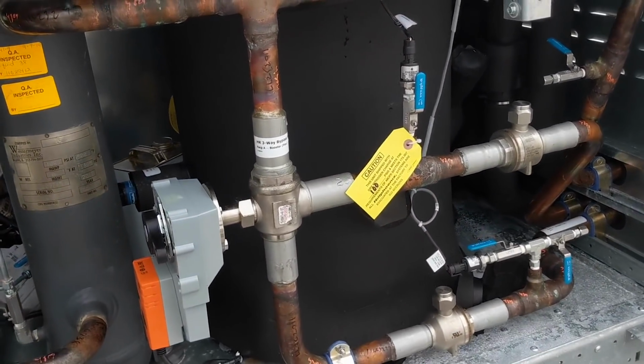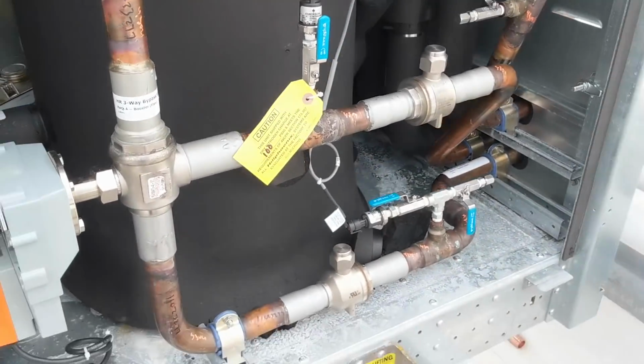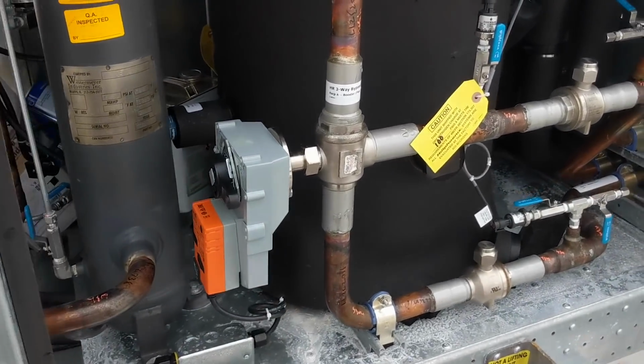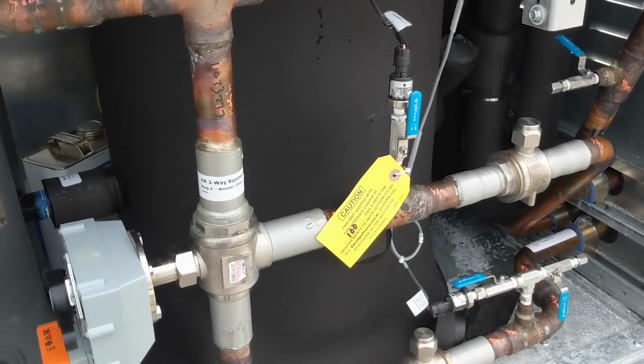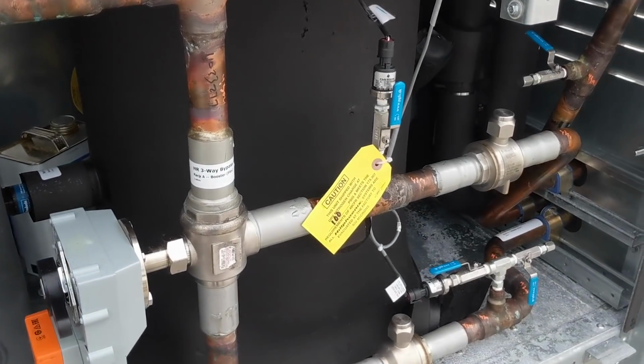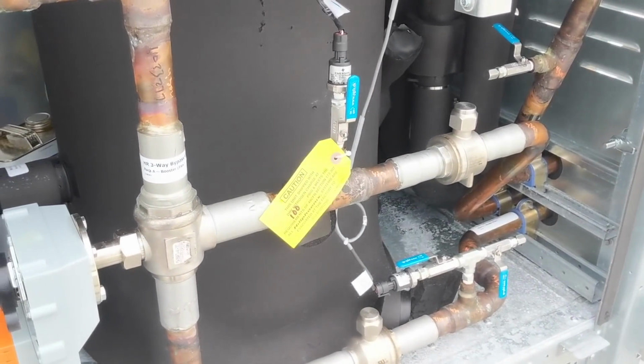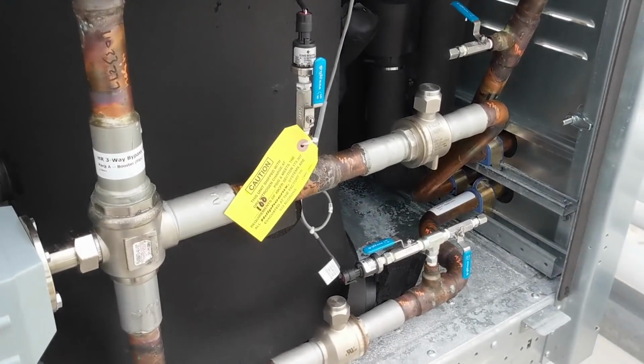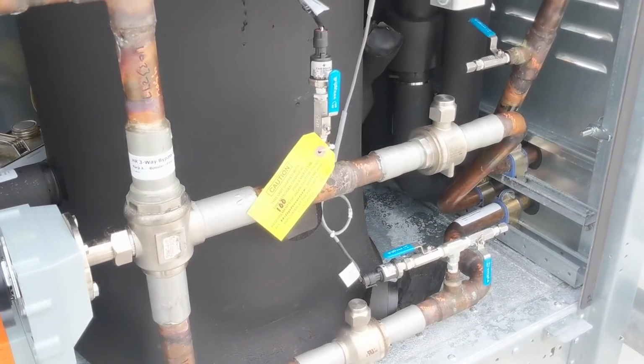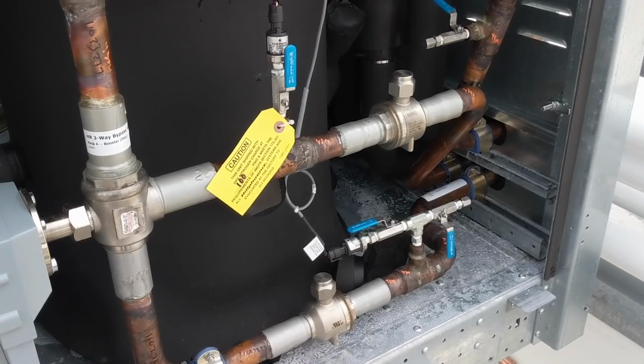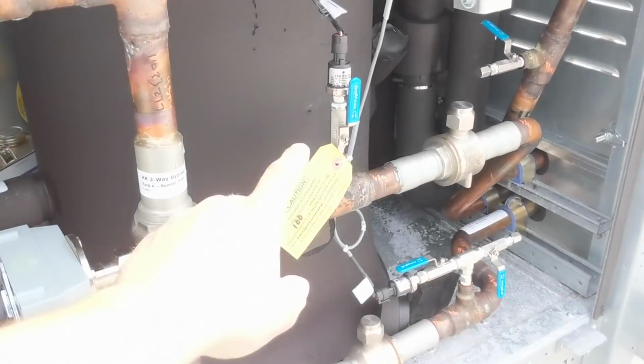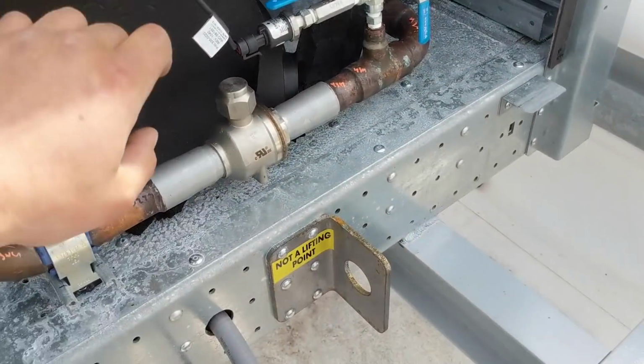So we're using discharge gas from the compressors, from the high side compressors, anywhere from 700 pounds to 1600 pounds. And we're sending this to one of our main store rooftop units to reheat the air. We got two transducers on here. We got one right here and we got one right here.